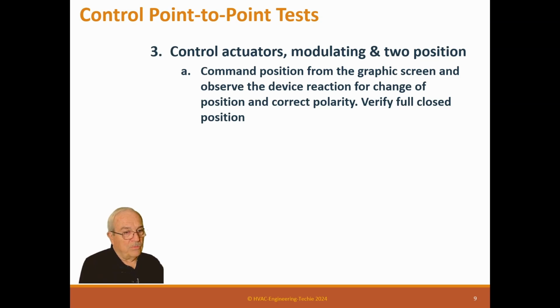And what happens is we're continuing to work while we're waiting for those stupid dampers to open, which can take forever. The reason it takes so long at a VAV box is they normally do a few rotations and stop, check where they're at, what's going on, check the sensor, and then go do a few more rotations. So they don't just do it in one full swoop like you think they would. They take a long time, so we'll do that. 100% open on an OBD damper, parallel blade damper: from 90% on, they don't do anything, it's 0. So it doesn't matter if they don't go full open, but it does matter that they go full closed.